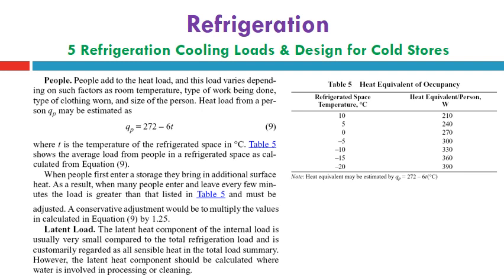You can consider the amount of heat equivalent per person according to the number of persons, and multiply for each person. For example, if we have a refrigerated space at 0 degrees and 10 people inside it, each person generates heat equivalent, according to this temperature, of 270 watts per person. Multiplying by 10, we have 2700 watts of heat generated by the people working inside this cold store.